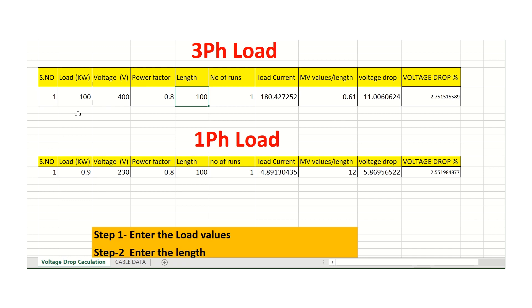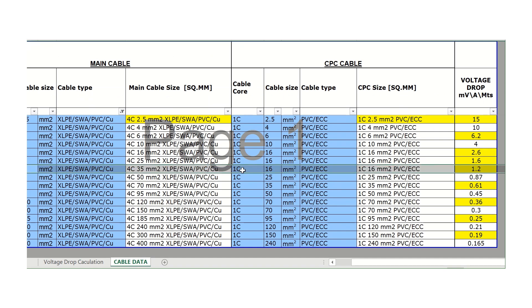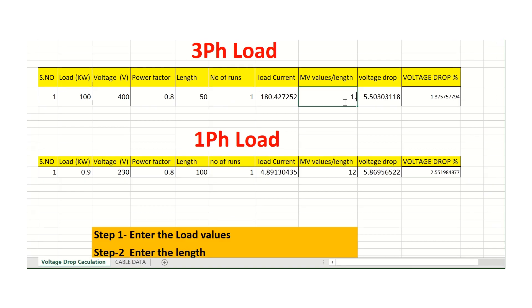Using the same 100kW load but reducing the length to 50 meters, we can try a 4-core 35mm² cable (MV = 1.2). Entering that value gives a voltage drop of 5.50V, well within limits. So when the length is reduced from 100m to 50m, the cable size also reduces from 4-core 70mm² to 4-core 35mm².